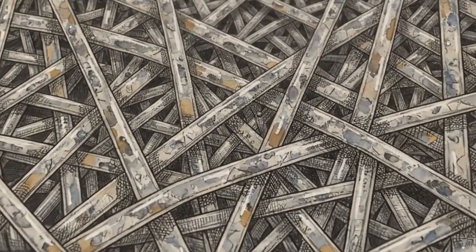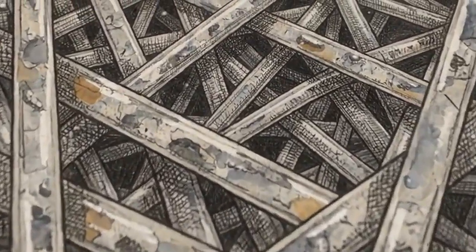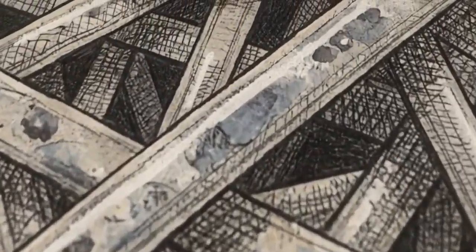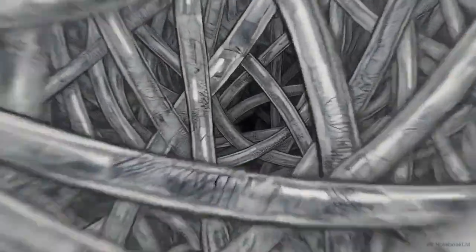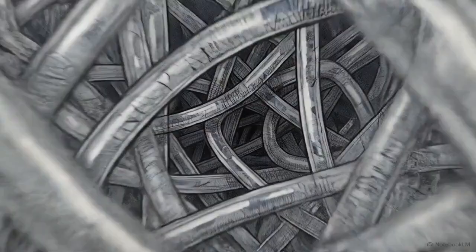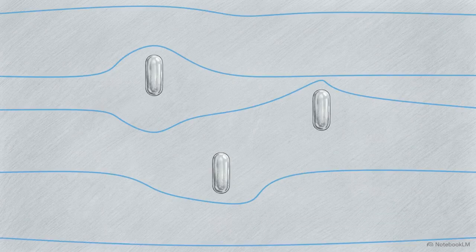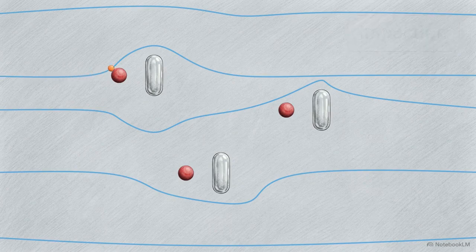While it accounts for larger debris, capturing microscopic threats requires the filter to exploit behaviors that go beyond simple physical blockage. Zooming past the human scale, a HEPA filter is not a uniform grid. It is a deep, densely packed, chaotic forest of three-dimensional glass fibers. Large particles have significant momentum. Unable to navigate the curved airstream around a glass fiber, they slam straight into it, a process called impaction.